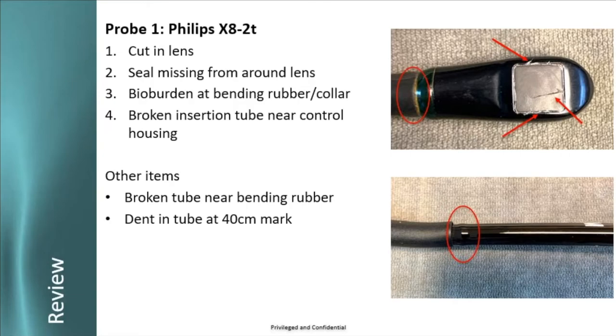It was a local hospital to me, and I called the biomed director. I said, I don't understand what you guys are doing, we're getting kinks way down here. Unless you're scanning giraffes or something, there's no way you can kink it down here, because the probe line only goes in so far when you're doing a transesophageal exam. It turned out they were putting it in this tube, and as they went around corners, the tube was snagging on doorways and cracking, and that was kinking the probe. It's kind of like a garden hose - when you kink it, that kink is there forever.